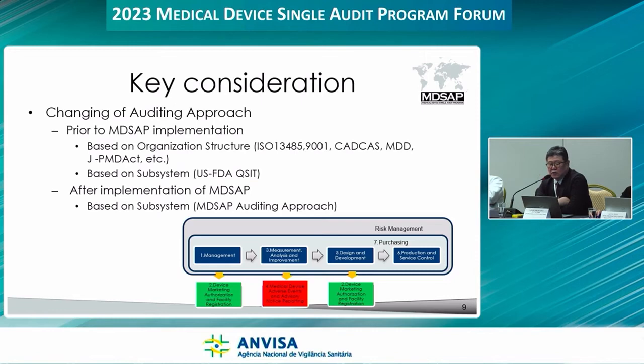Another change in the audit methodology also needed to be noted. In certifications such as ISO 13485 or MDD schemes, it was regulated to conduct audits on the organization, by organization, in each manufacturer's or manufacturing site. On the other hand, for US FDA schemes, we have to consider the audit method based on the QSIT. We had to deal with both audit methods prior to the introduction of MDSAP.